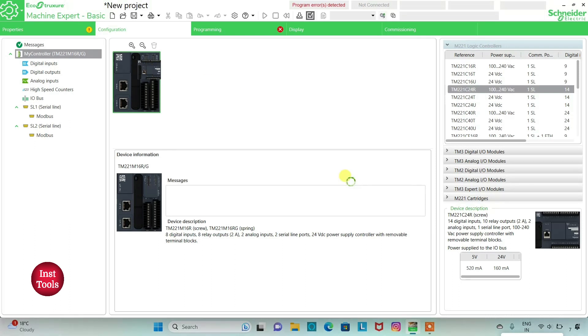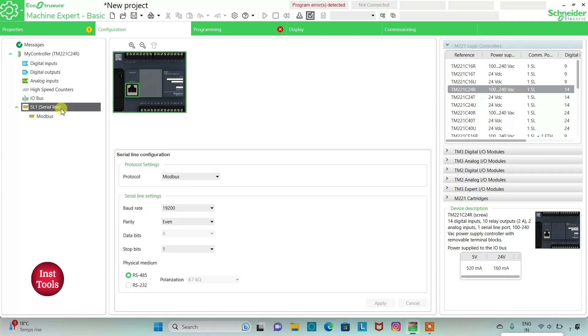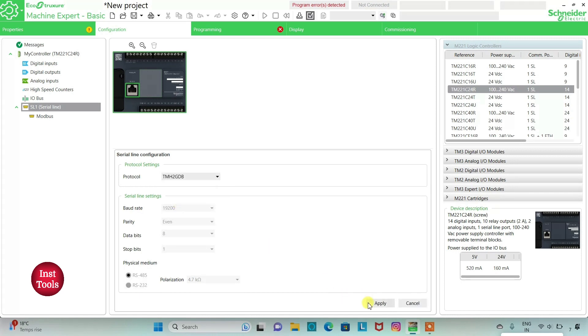Click yes to replace. The logic controller I am using is TM221 C24R, which has 14 digital inputs, 10 relay outputs, two analog inputs, one serial line port, 100 to 240 volt AC power supply, with removable terminal blocks. I can also go to Serial Line and select the protocol as TMH2GDB, then click Apply.